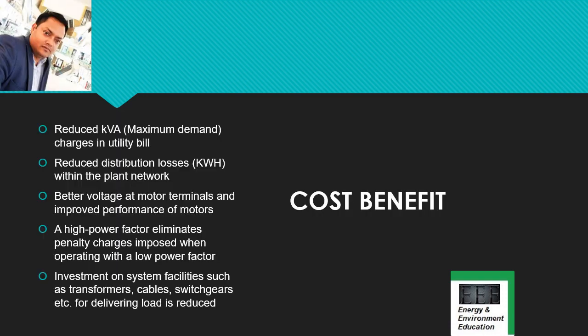The cost benefit with improvement in power factor is a very important part. You may be asked short type questions or parts of long questions explaining the different cost benefits. With improvement in power factor: there is a reduction in KVA or maximum demand, reduction in distribution losses in the network, better voltage at motor terminals and improved motor performance, less penalty or elimination of penalty charges due to low power factor, and reduced investment in system facilities like cables, switchgear and transformers.